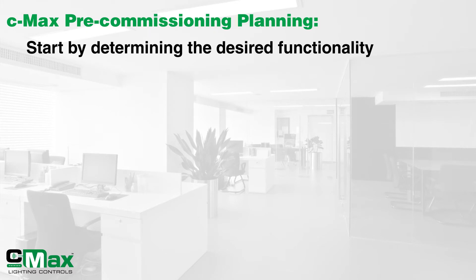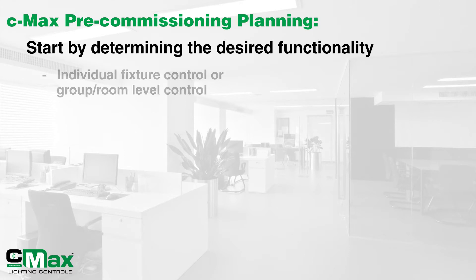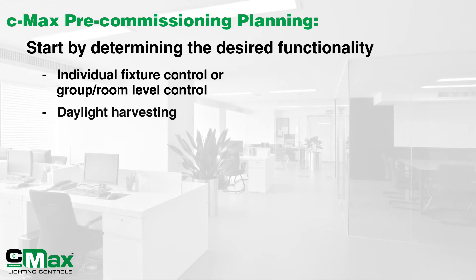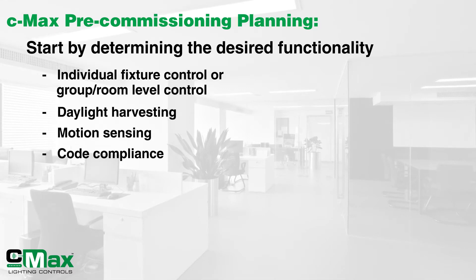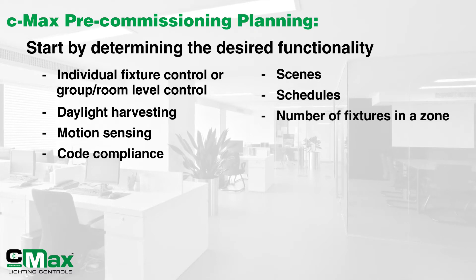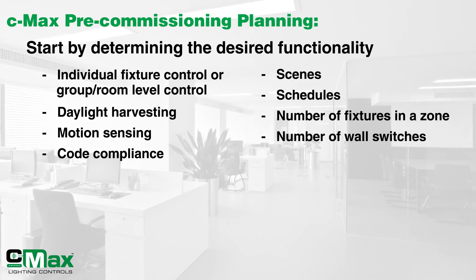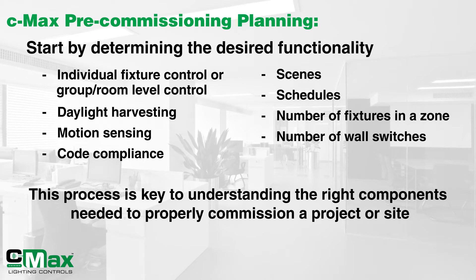First, it is always good to do some pre-commissioning planning to determine the desired functionality in the actual installation area. Considerations such as individual fixture control or group level control, daylight harvesting, motion sensing, and code compliance, scenes, schedules, number of fixtures in a zone, total number of wall switches, and more are key to understanding the right components needed to properly commission a project or site.